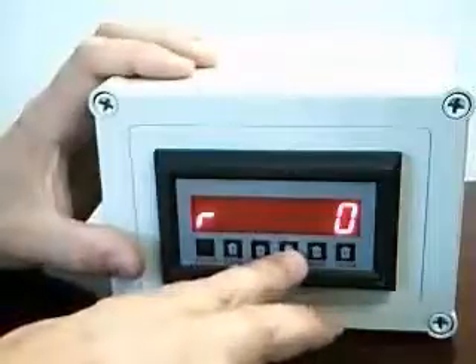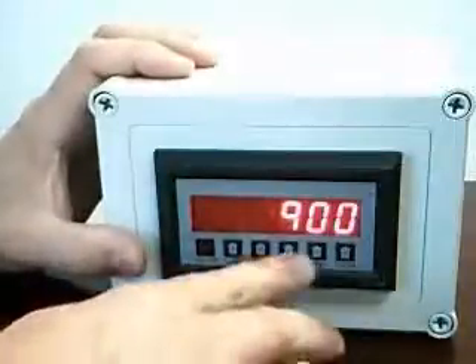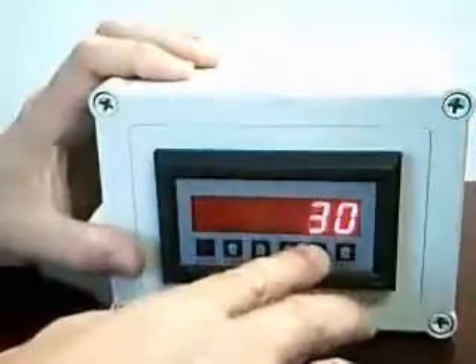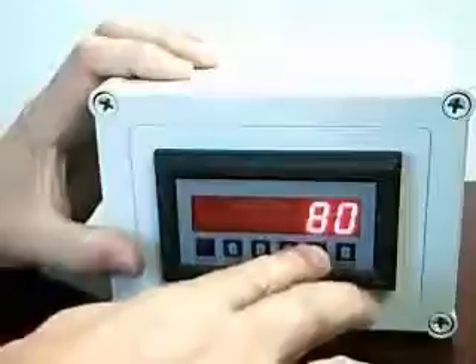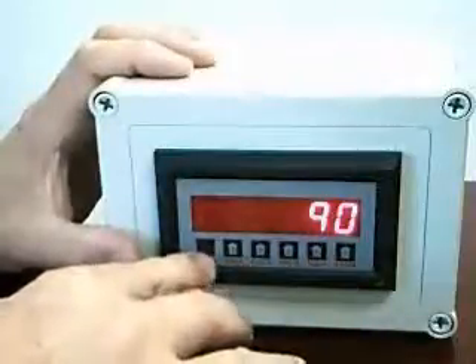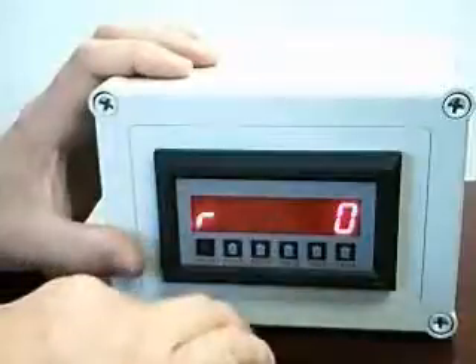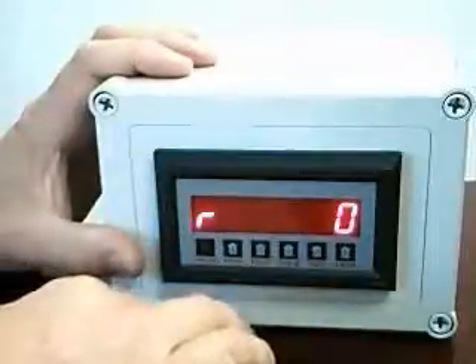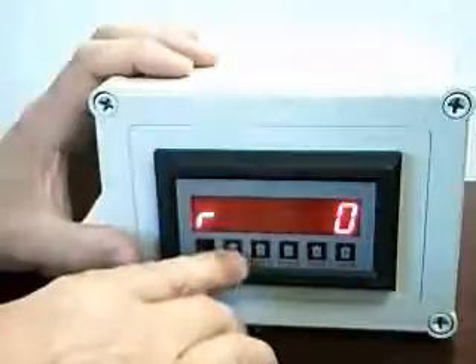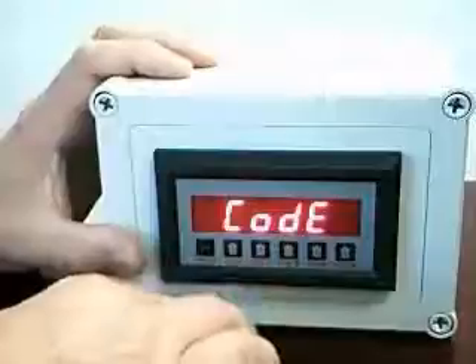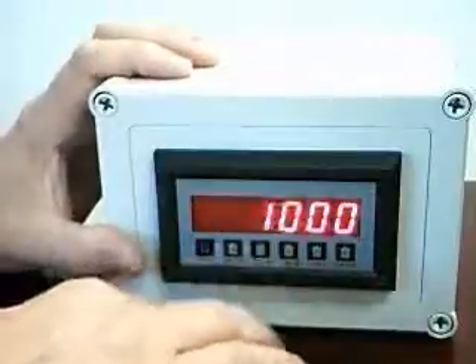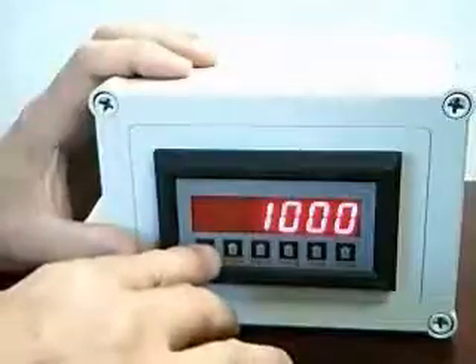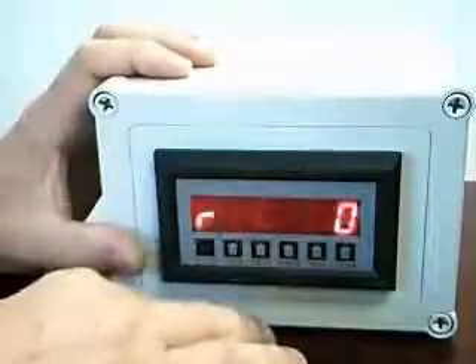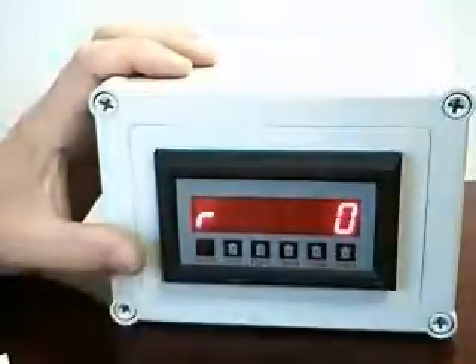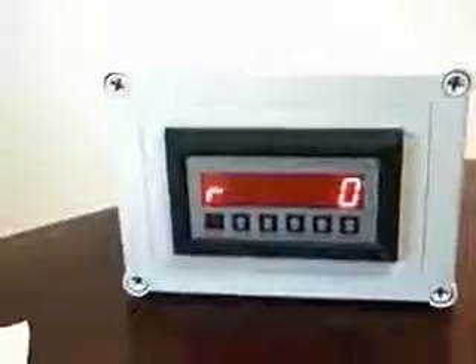I'll now go through and change the second alarm point to 90. Once I have a satisfactory display appearance, I can hit enter. At this point, we can lock the unit and the setup is complete. We had predefined a password of 1000, so I'm entering that number and then pressing enter. The unit responds that it is now locked. This completes the basic setup of the MiniTrol, and the unit can now be put into service.